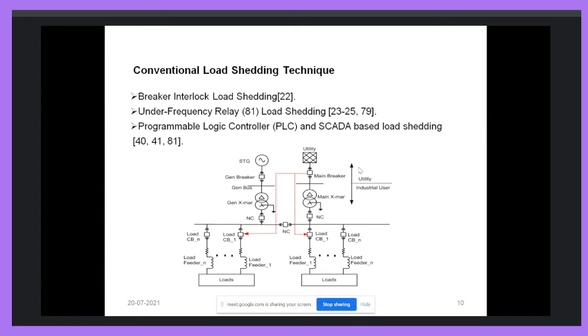Here you can see the diagram of the under frequency breaker interlock based load shedding scheme. There is a generation; the STG is a generator, and this is a utility grid. We have connected this industry STG with the utility grid. This is a circuit breaker which is normally closed; NC is the normally closed symbol. Normally it operates in parallel with the grid, and these are the loads. Whenever the power requirement is more than the in-plant generation, the power will be drawn from the utility. This type of load shedding technique is designed for the worst operating scenario.